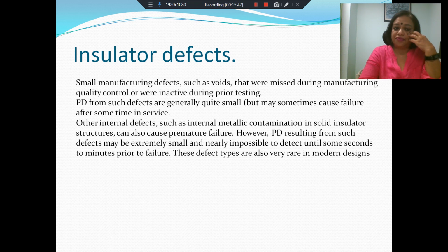So PD resulting from such defects may be extremely small and nearly impossible to detect until some seconds to minutes prior to failure. So the only thing that we can do is ask the manufacturer to be more careful and to control the presence of such defects at the preliminary stage. Thankfully, in modern design, such defects are rare, and we are moving to a situation where we don't have to worry too much about this.